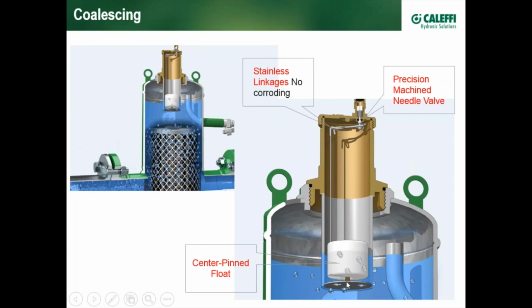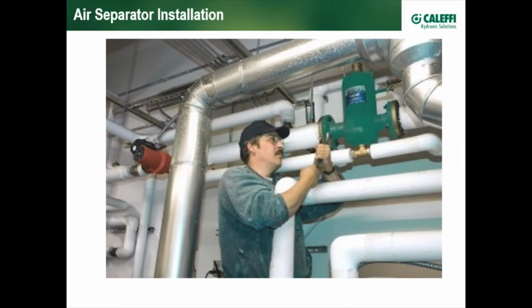A nice unique feature of Caleffi, and very precision ground needle valves, because right through these O-rings that the needle valve is sealing up against is all the air goes automatically in the system, whether it's a small air vent or a 12-inch pipe diameter air separator from Caleffi. All the air ends up going through a needle valve through an O-ring such as this. So attention to detail is very important, and I think differentiates ourselves from many players in the coalescing market, if not all players. Here's a contractor wrenching in up in Montana, a Caleffi air separator.